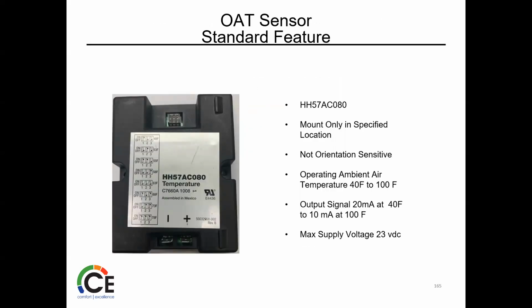That's a blast from the past. I was going to change it, but I haven't seen that in so long I left it there. Standard outdoor sensor. Of course, now we're using the newer version of it, but outdoor ambient air, 40 to 100 milliamp signal. So when we're testing for signal, you've got to have the capability of testing milliamps. Max supply voltage 23 DC. So again, the dip switches on this, just like a lot of the newer ones, determine what temperature you want it to monitor.